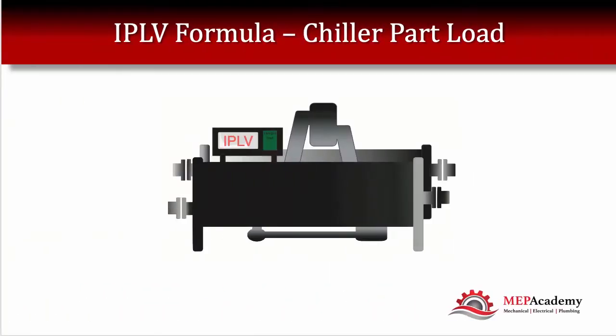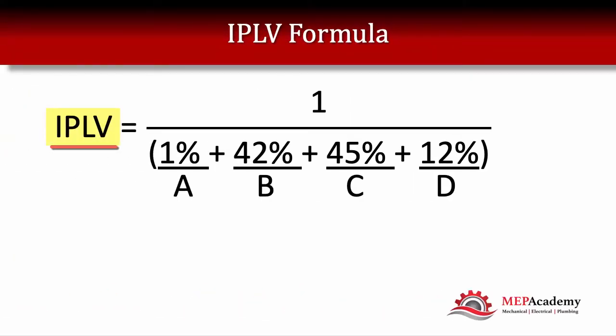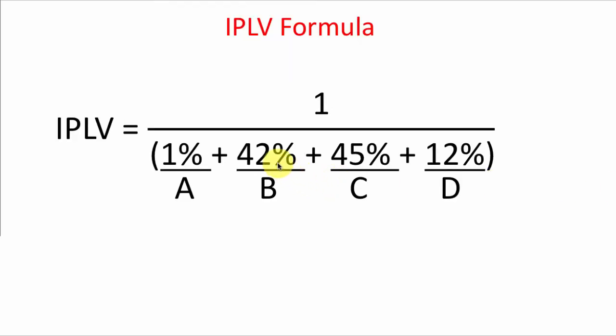The IPLV formula is 1 over the sum of four points: A, B, C, and D. These represent the efficiency of the chiller at different loads. Condition A accounts for 1% of operating time, condition B for 42%, condition C for 45%, and condition D for 12%.